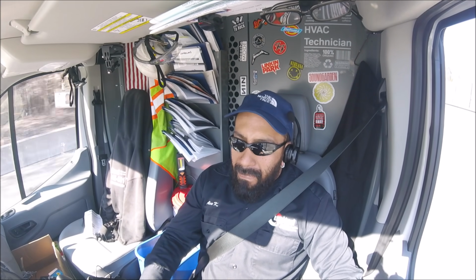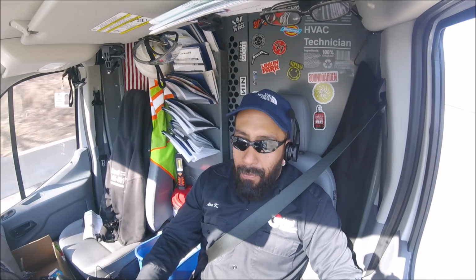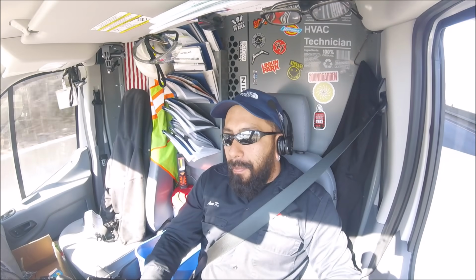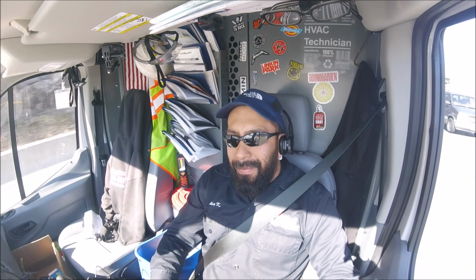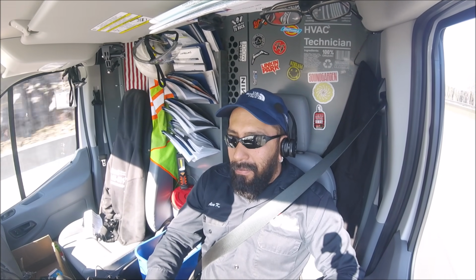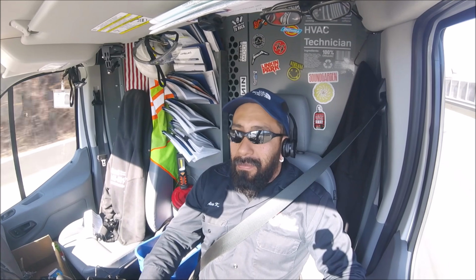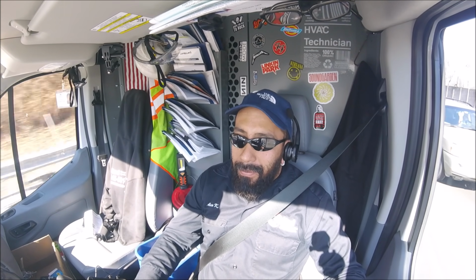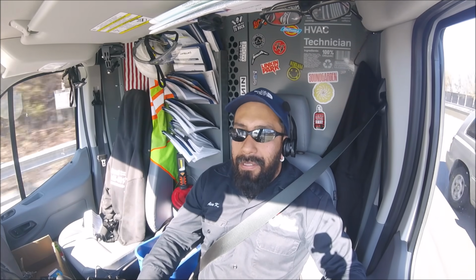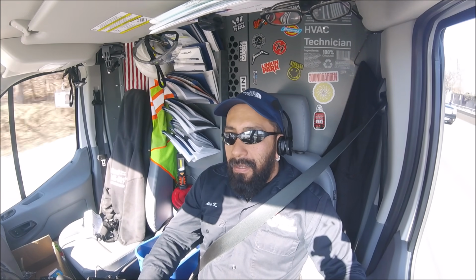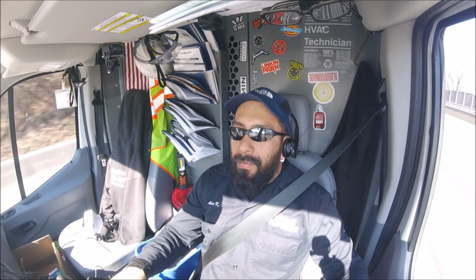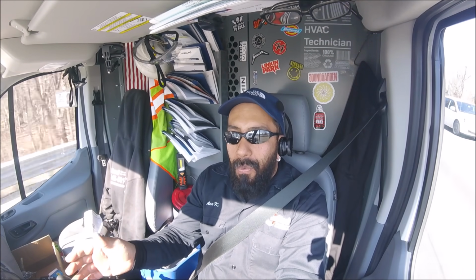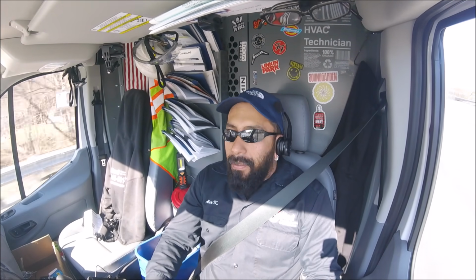I was looking at both units and they looked the same, with pretty close serial numbers. So I thought, if this one already has a crack, probably the other one has a crack too. I couldn't leave the place thinking there might be a hole in the other heat exchanger - you know how it is, everything seems fine until somebody's dead, and then it all comes out. Like if you go up on a roof and don't check one of the units, then the next day something happens with that unit you didn't check.